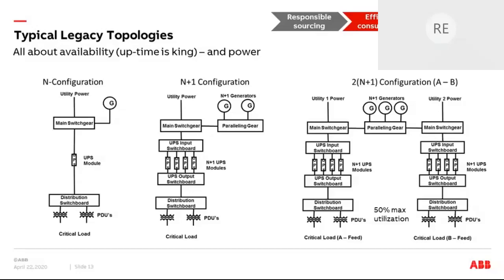So we added more generators. If we needed 3 generators, we have 4, so that one could fail and you'd still carry the whole load. Similarly, on the UPSs, we added N+1, so if we had 3 UPSs, we would use 4. This led to some redundant equipment, but it also vastly increased the uptime and availability of your data center.